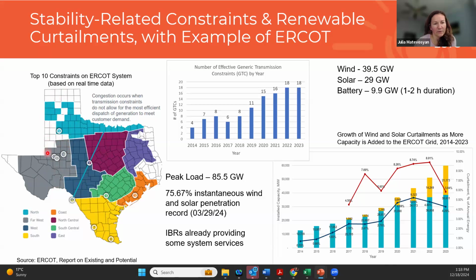Primarily wind and solar resources are concentrated in the west part of the grid. Traditionally, these parts of the grid don't have much load, so they're far away from load centers, and most synchronous generation is on the east side. So we're far from load centers and far from synchronous generation, which causes weak grid conditions in the Texas Panhandle and even in West Texas, with some voltage stability limitations and risk of control interactions.